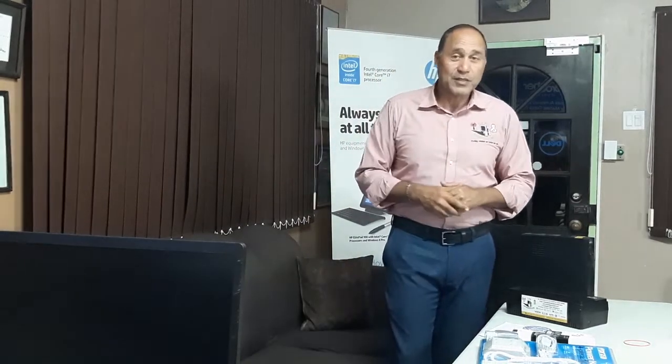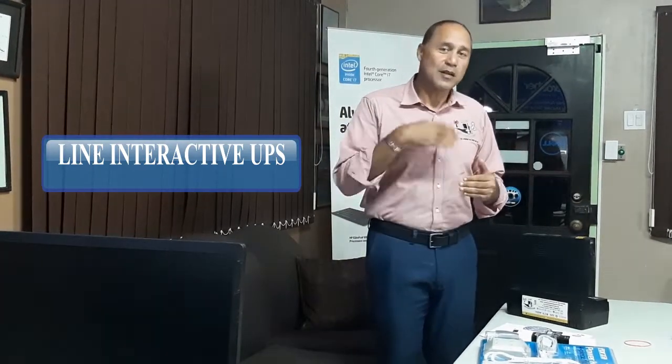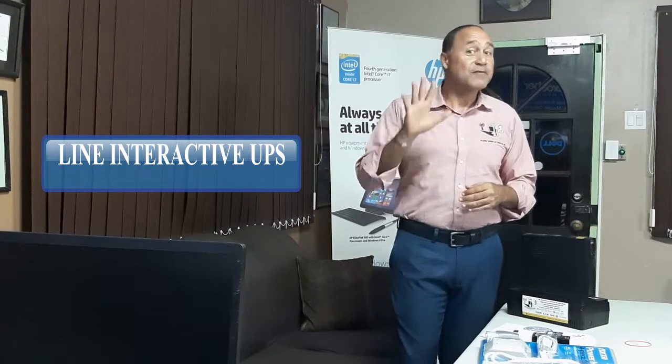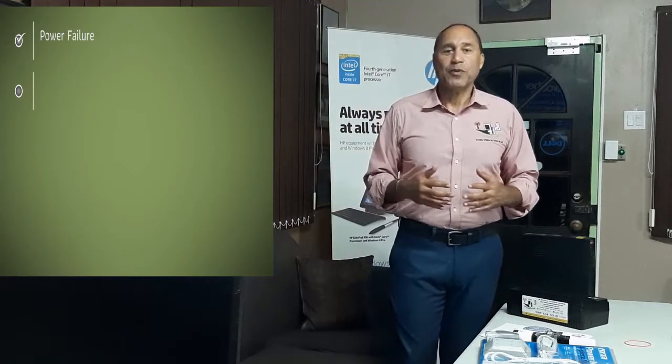The next line of UPS is what is known as a line interactive UPS. That UPS, of course, is going to cost a little more, and it protects us against 5 of the power problems out there. It's line interactive because it senses when there's a problem along your power line. If you have low voltage, it will boost that power a little bit and carry it up to what the normal voltage should be, and give that power to what your machine should be having.